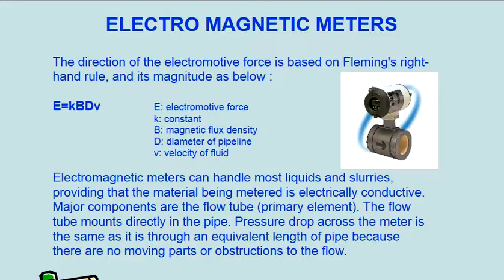Electromagnetic meters can handle most liquids and slurries, providing that the material being metered is electrically conductive. Major components are the flow tube primary element. The flow tube mounts directly in the pipe.